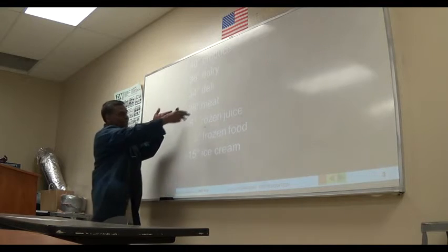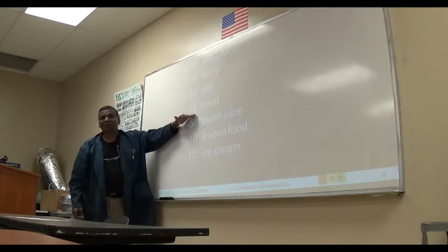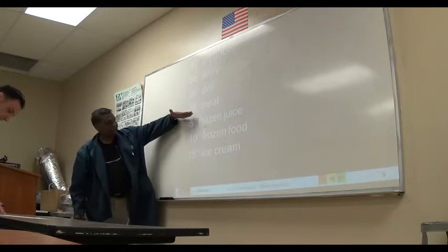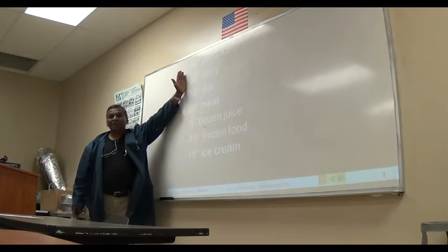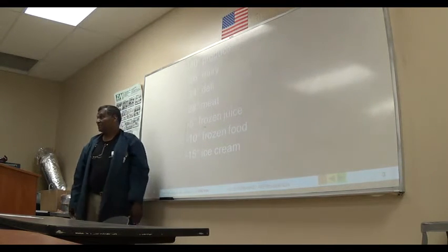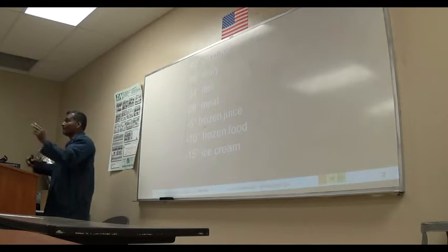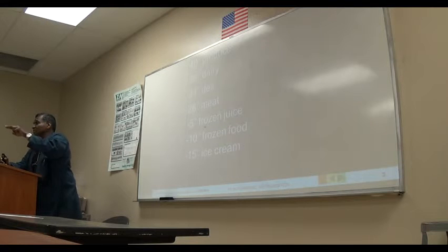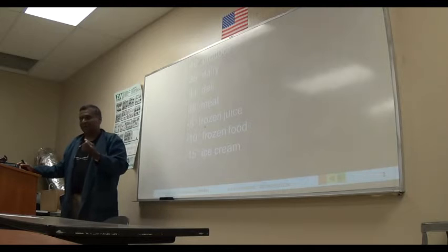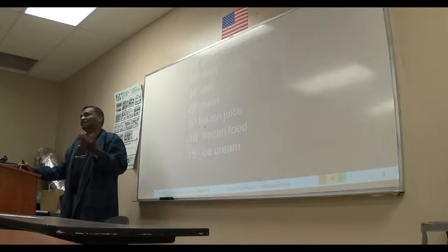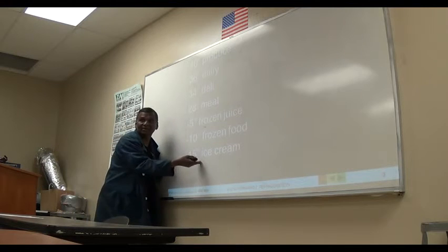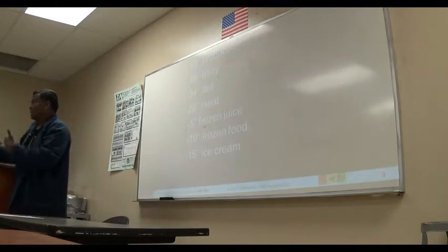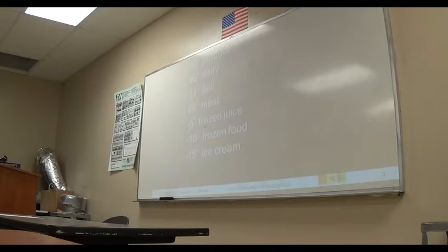And these guides will actually give you an idea what type of refrigerant you're going to need. From here going down, chances are we'll use R404A refrigerant, and from here going up, R134A, because these are the higher temperatures and these are the lower temperatures. R404 and R22 are kind of mirror images on the PT chart. R404 at 0 PSIG should boil somewhere around negative 43 or negative 45 degrees, so you will be able to get to these lower temperatures without that compressor going into a vacuum. Normally I will see compressors running as low as about 3 PSI on the suction side.